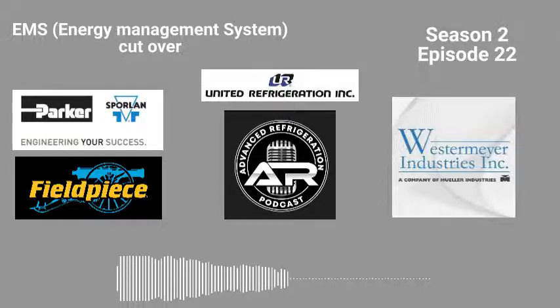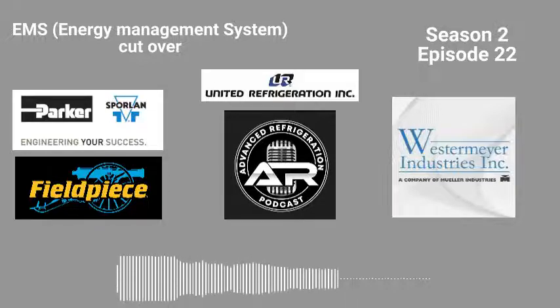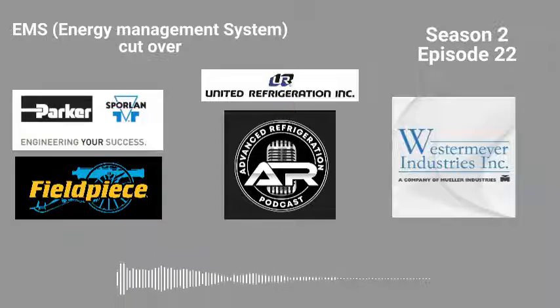I've had to do outputs too, but in a way that is non-hackish — I wrap them in the plastic wrap like the OEM would. I do not splice anything, not an input, not an output, with wire nuts, gel caps, anything. Everything, if I have to extend it, goes on a terminal block. I've been religious about it and it's made everything a lot easier. When I do a switchover and have boards on a door, I can pre-run all the wires and pre-mark everything, so during the switchover I'm just moving things to the terminal block one by one. Super easy and it looks clean.